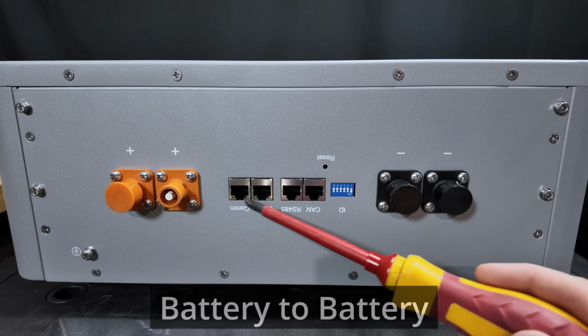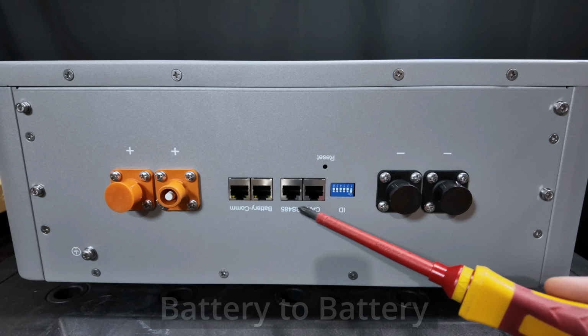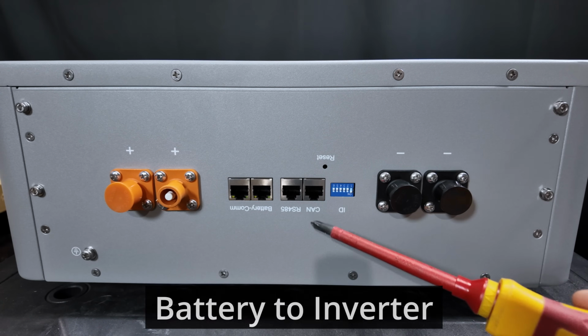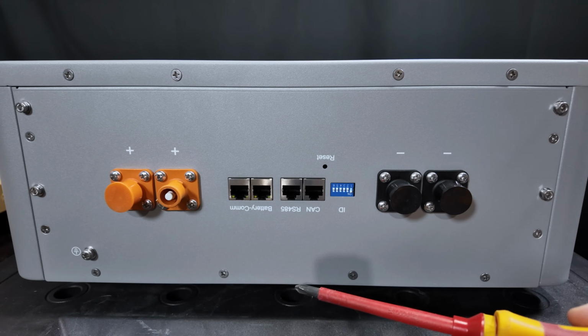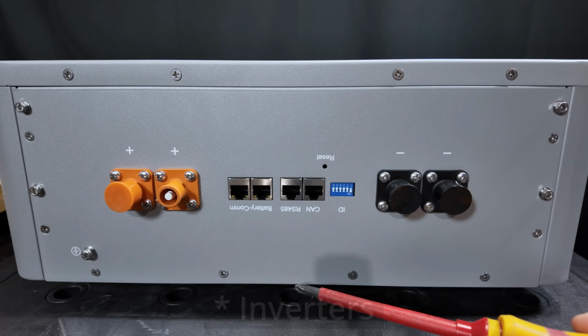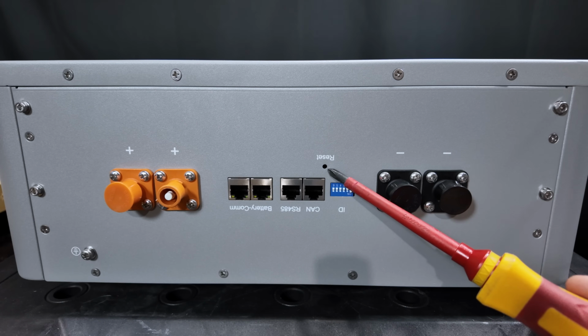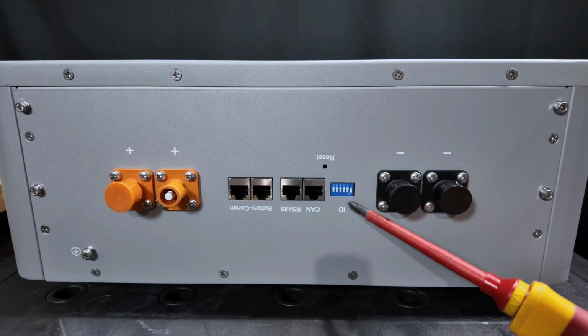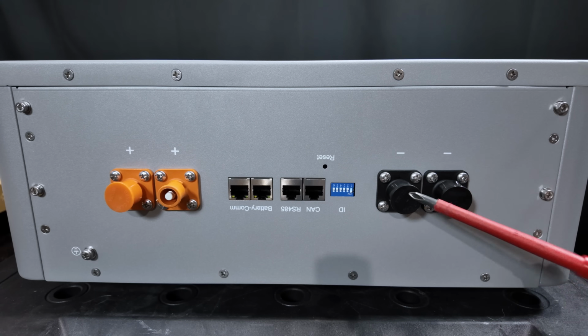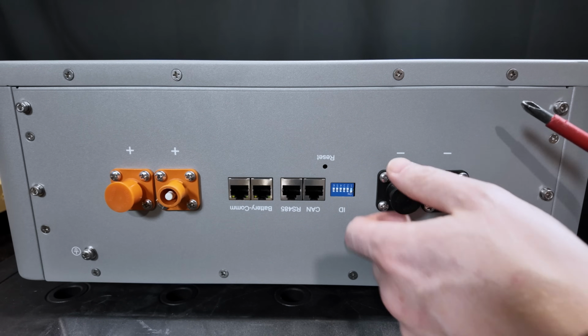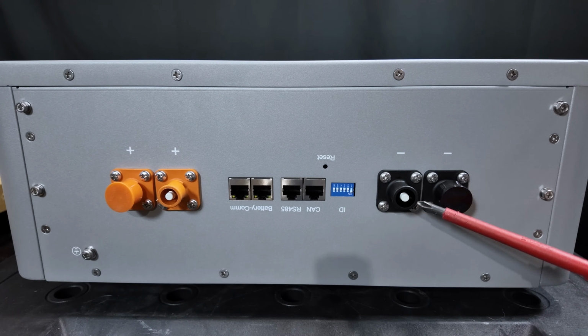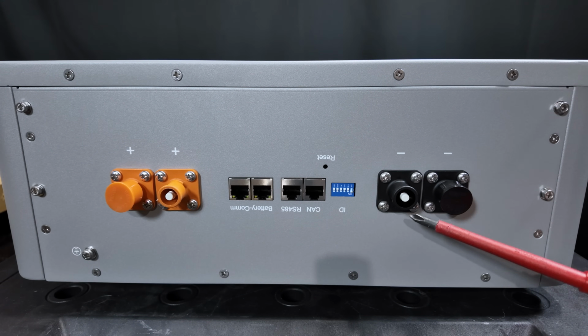These 2 are our battery communication ports. This has RS-485 and CAN communication capability to communicate with a handful of different BMSs. We have a reset button right here, our ID dip switches for identifying the battery. You can daisy chain up to, I believe it's 64 in parallel. And then we have our negative battery terminals, again with the Degson quick connect connectors.